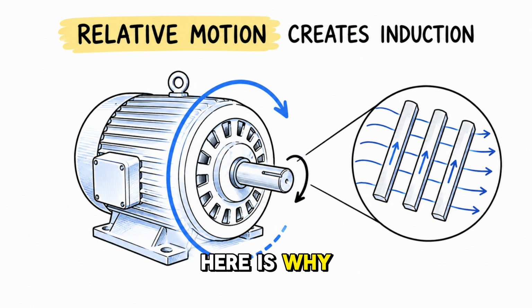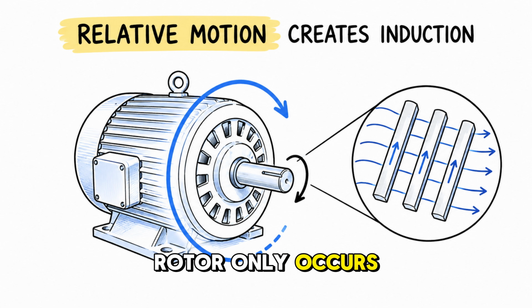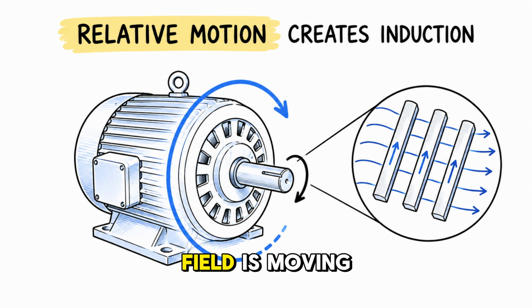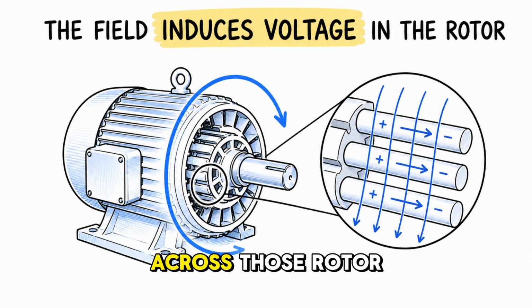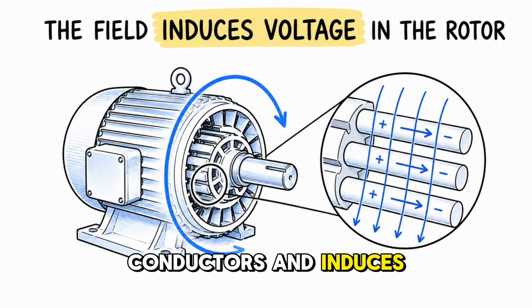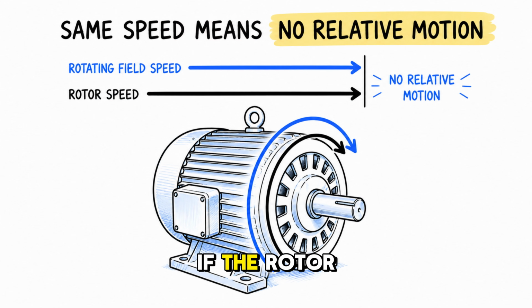Here is why. The induction inside the rotor only occurs because the rotating magnetic field is moving relative to the rotor conductors. The field cuts across those rotor conductors and induces a voltage in them. If the rotor were somehow spinning at the exact same speed as the rotating field, that field would no longer be moving relative to the rotor.